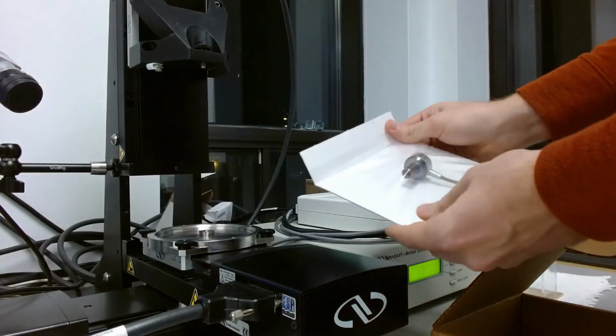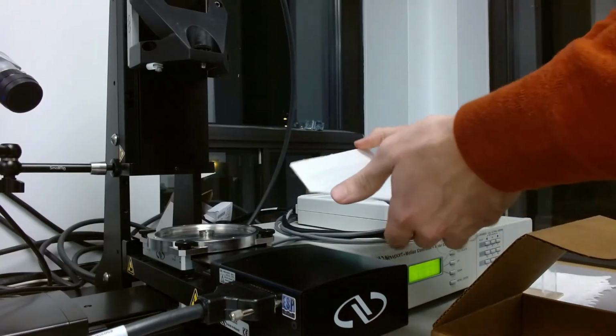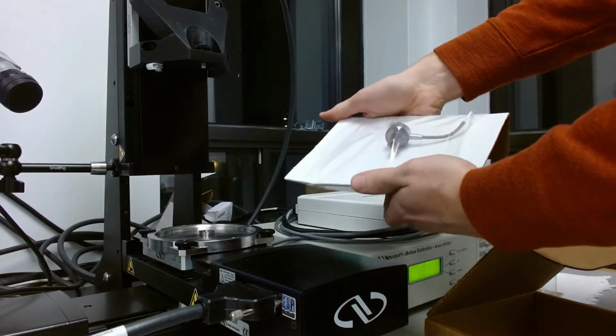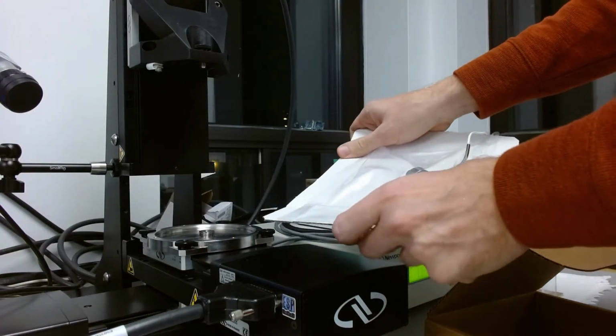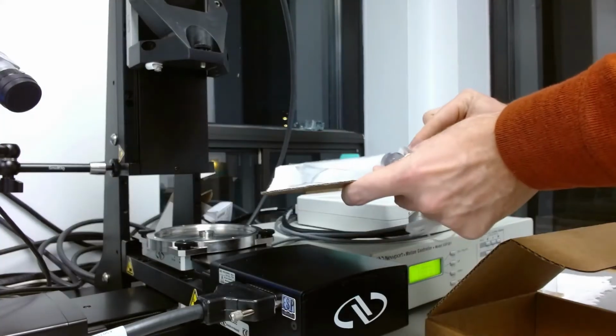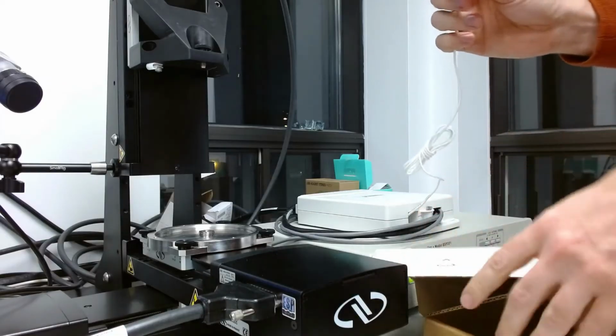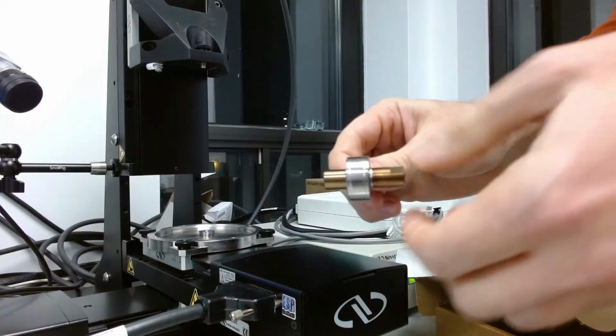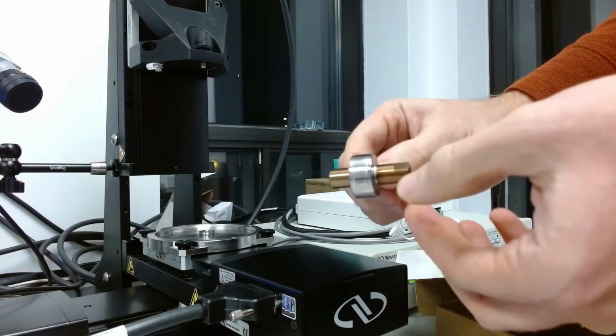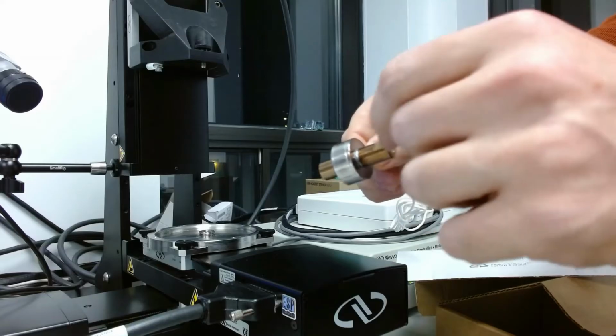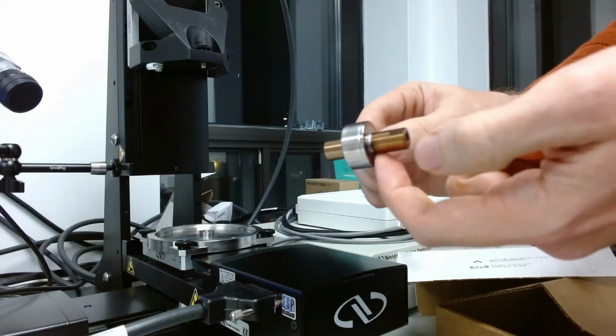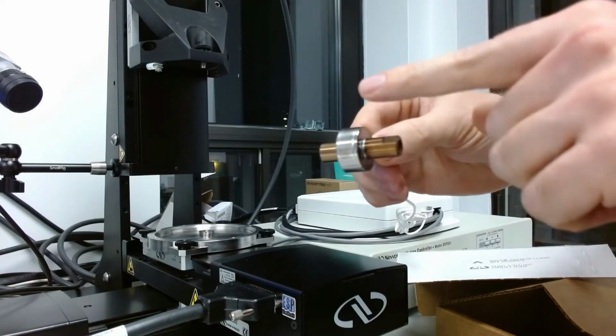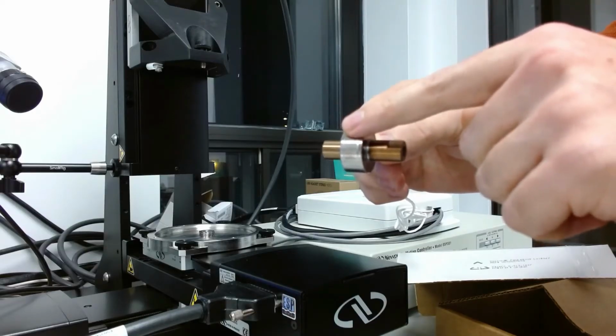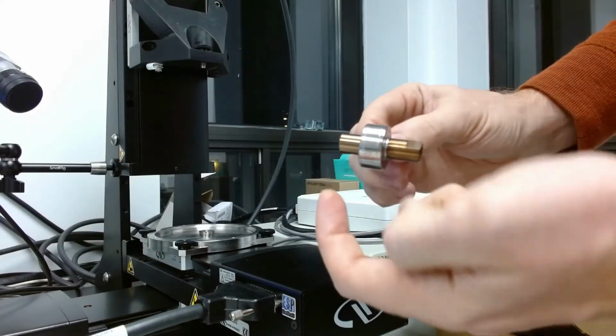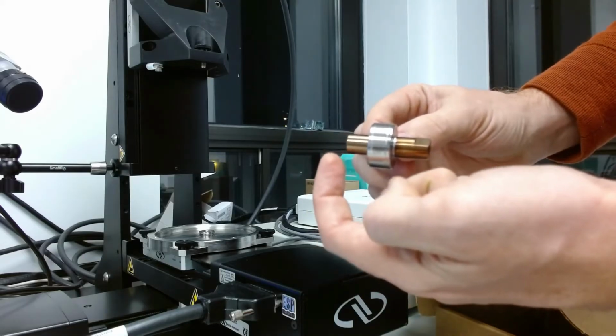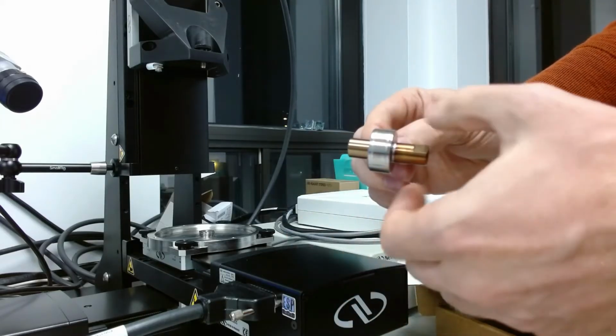In the box, there should be a plastic film wrap. What we're going to do is undo the sides in cardboard, then take out the load cell. The load cell should only be handled by the center or by the part with notches. This part, if we look closely, is actually welded to the body of the load cell. So touching either this side or the body will not affect the load, but ensuring that we never touch the side where load is applied at the same time as any of the other parts of the load cell.